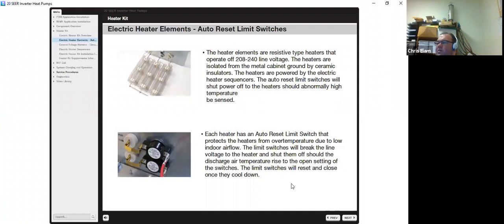So you can get that from a dirty filter, dirty coil, blocking off supply vents, and a number of things that will reduce the airflow out of the furnace. The limit switches will break the line voltage to the heater and shut them off until the air temperature cools and allows those switches to reset.